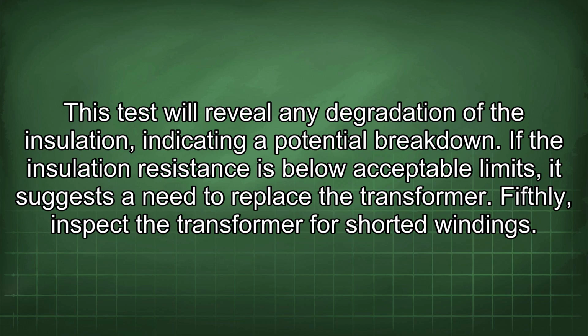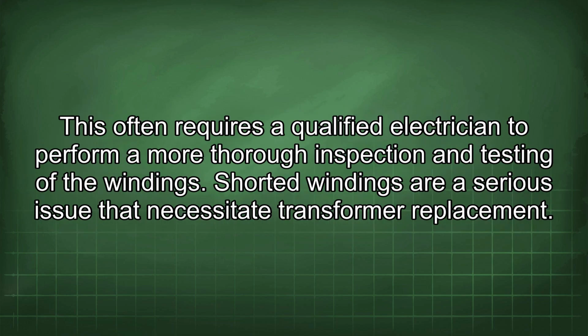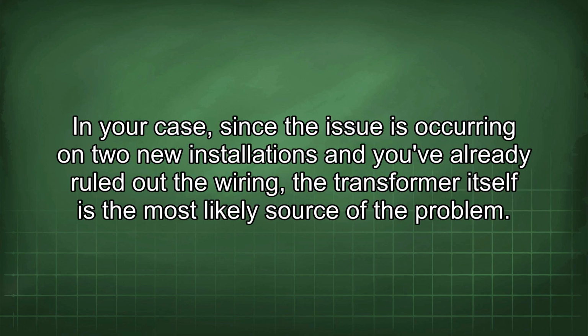Fifthly, inspect the transformer for shorted windings. This often requires a qualified electrician to perform a more thorough inspection and testing of the windings. Shorted windings are a serious issue that necessitate transformer replacement. In your case, since the issue is occurring on two new installations and you've already ruled out the wiring, the transformer itself is the most likely source of the problem.